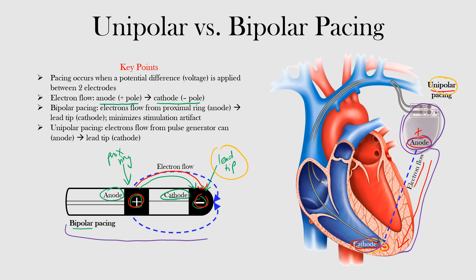With bipolar pacing, the entire lead is inserted so that you have your anode and cathode located very close to each other within the heart. This minimizes the stimulation artifact because the electrons do not have to travel so far — they travel from anode to cathode within that lead. So that helps minimize stimulation artifact with bipolar pacing modes.